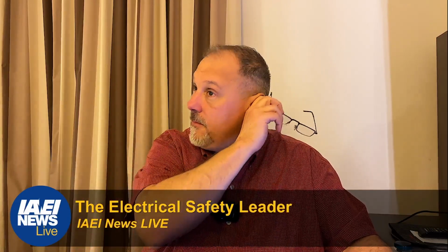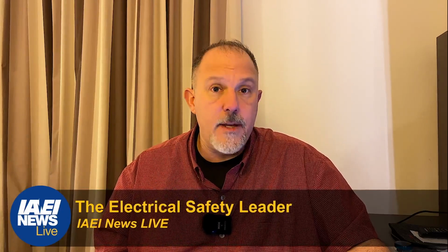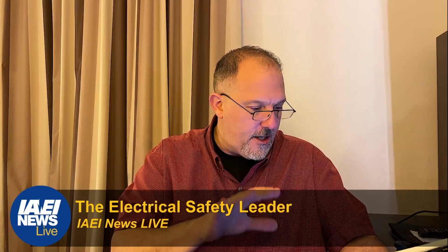So if you in your mind are picturing a duplex receptacle as a single receptacle, that would be incorrect. And in some cases in the NEC, when it calls for an individual branch circuit supplying a receptacle, that's not a duplex. You can't put a duplex. When it says supplying a receptacle, that means singular, that's one. That is not a duplex receptacle. That would be two. All right, so that's the definition of the receptacle.